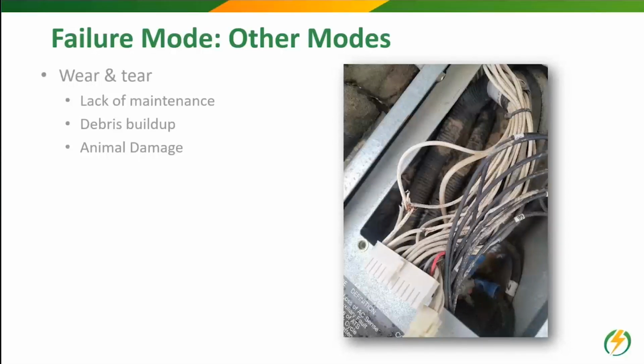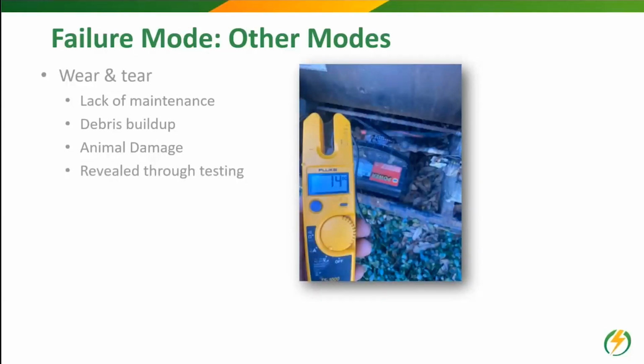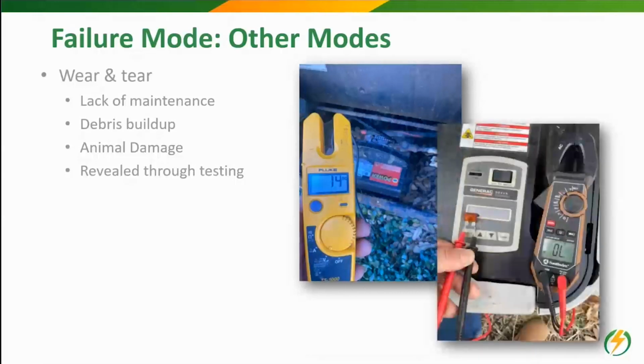Now, these are all issues that can be identified with normal maintenance before a power outage comes and the generator doesn't work. A large number of these issues can be identified through meter testing of the numerous components. A good technical review includes a review of the entire system to rule out as many possibilities before determining the one or multiple things that caused the system to fail.